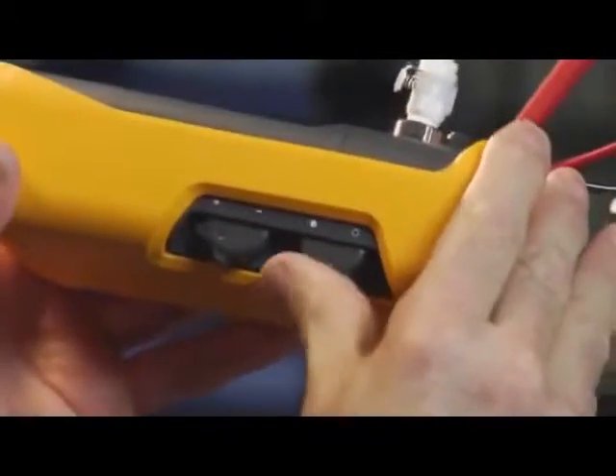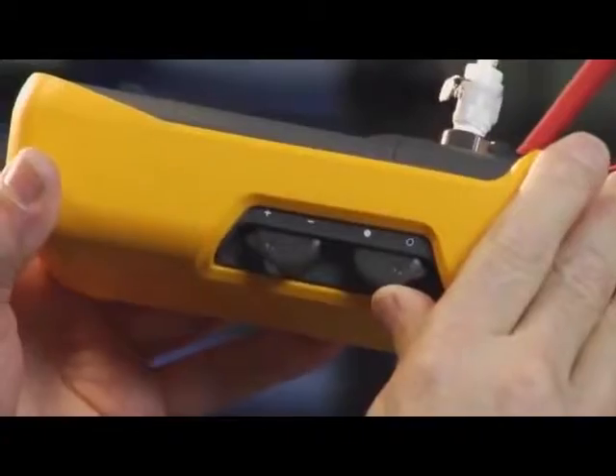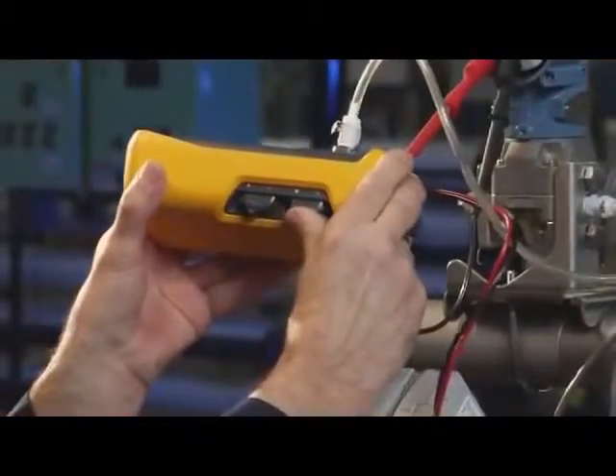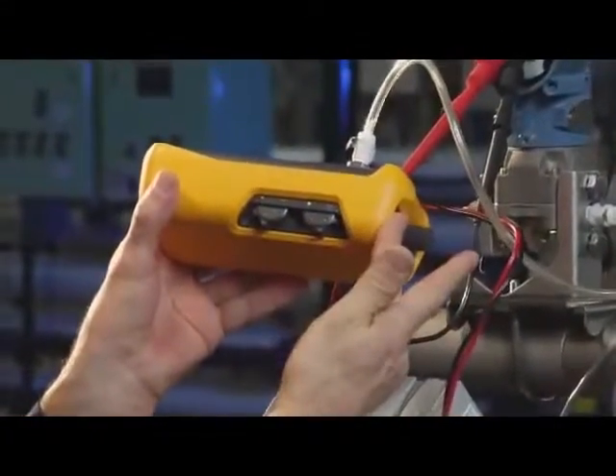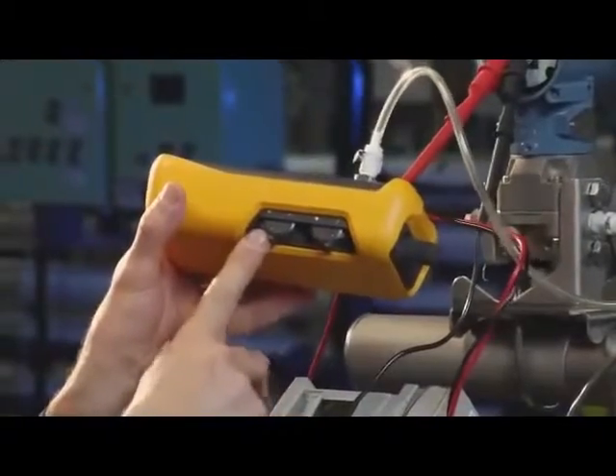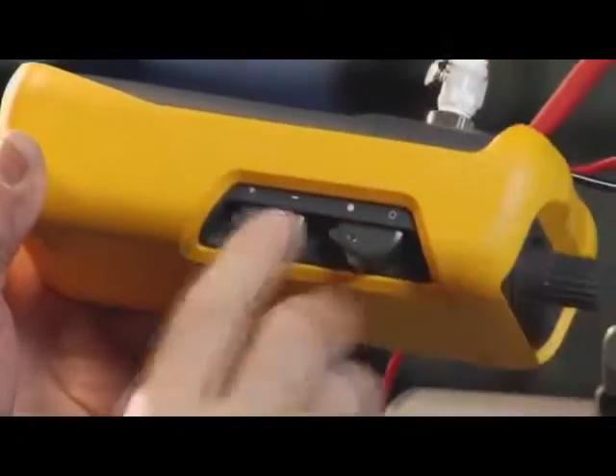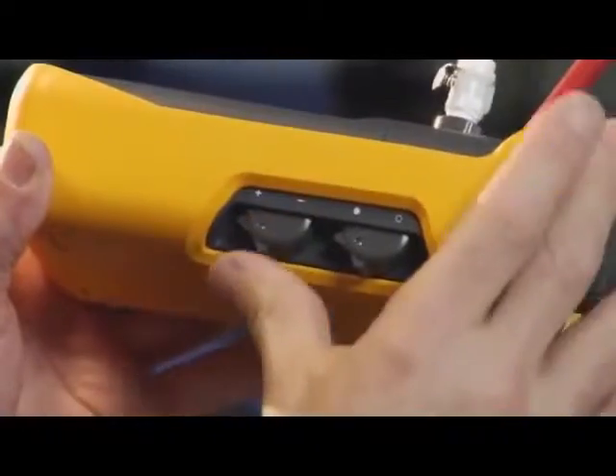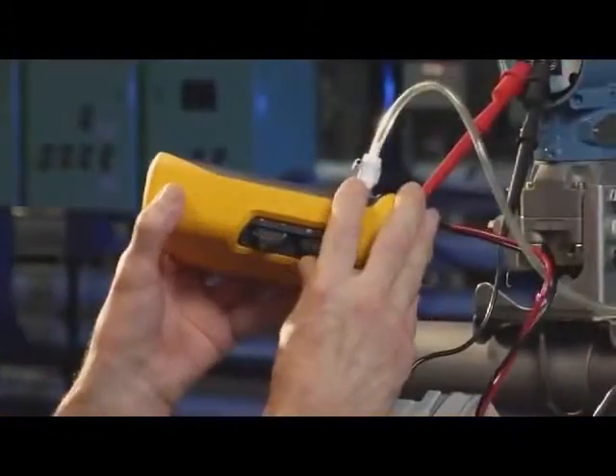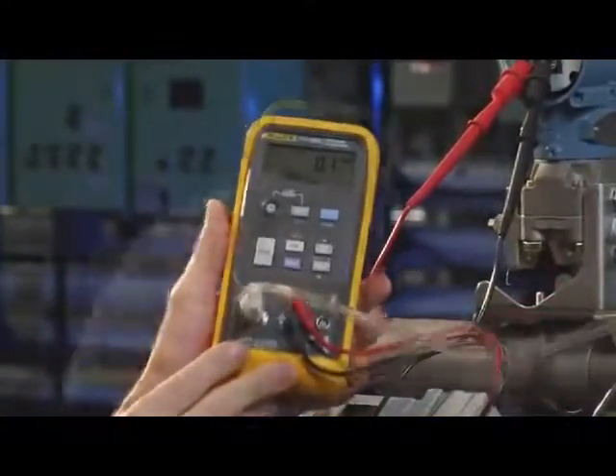The best way to do this is to vent the atmosphere. We do that with these controls. Open the vent valve. The vent valve can be opened or closed. Open for measuring the 0 inches of water point. This pressure vacuum switch allows you to pump either positive pressure or negative pressure. For this example, we're going to measure positive pressure.